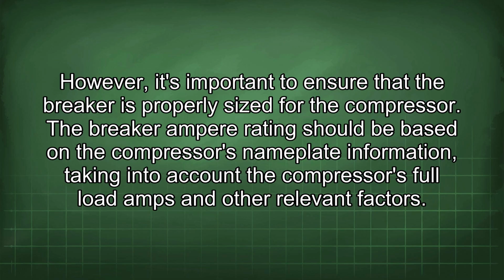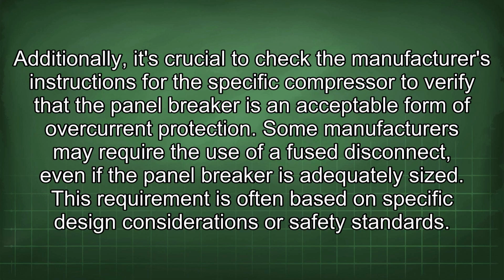The breaker ampere rating should be based on the compressor's nameplate information, taking into account the compressor's full load amps and other relevant factors. Additionally, it's crucial to check the manufacturer's instructions for the specific compressor to verify that the panel breaker is an acceptable form of overcurrent protection. Some manufacturers may require the use of a fused disconnect, even if the panel breaker is adequately sized. This requirement is often based on specific design considerations or safety standards.